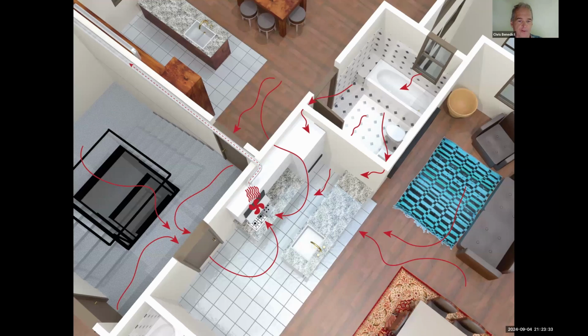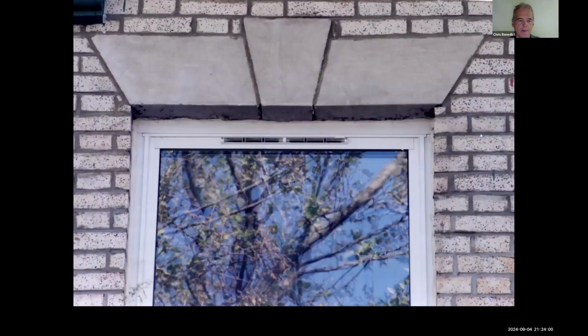The exhaust only has disadvantages. You see, there's air coming from the adjacent bathroom into these people's kitchen. It's coming from the hallway through the entrance door to the apartment into the kitchen. It's going all over the place. You can't plan it. Exhaust only is okay. It's coming through leaks, which is not great, but it's okay. It's the dominant type in this country.